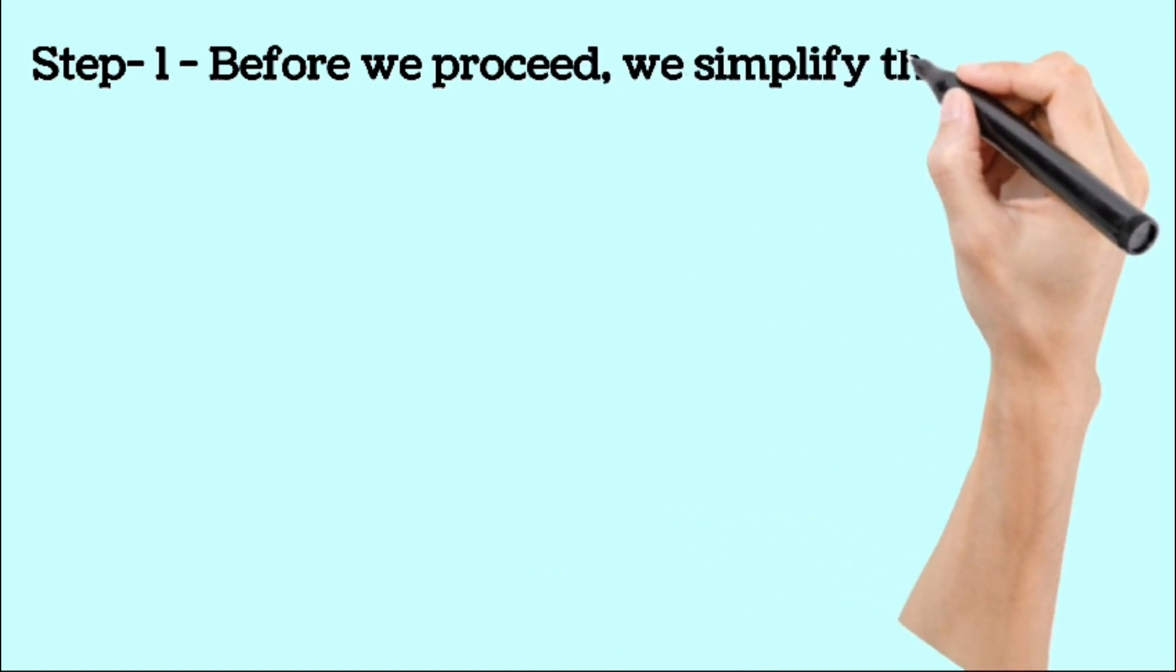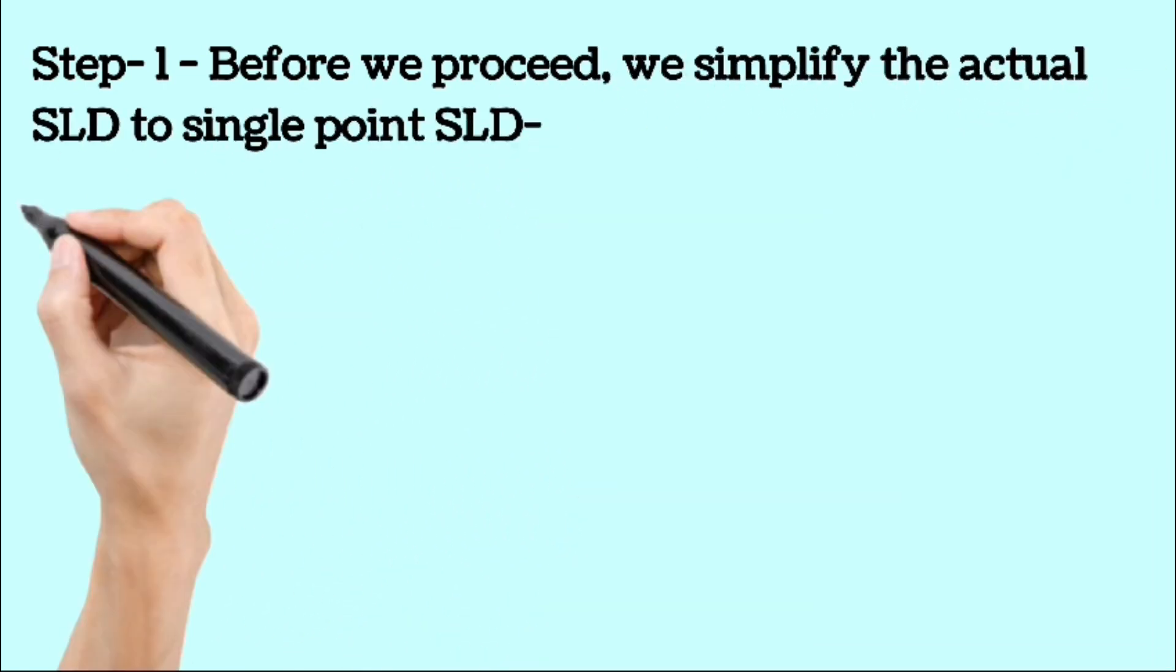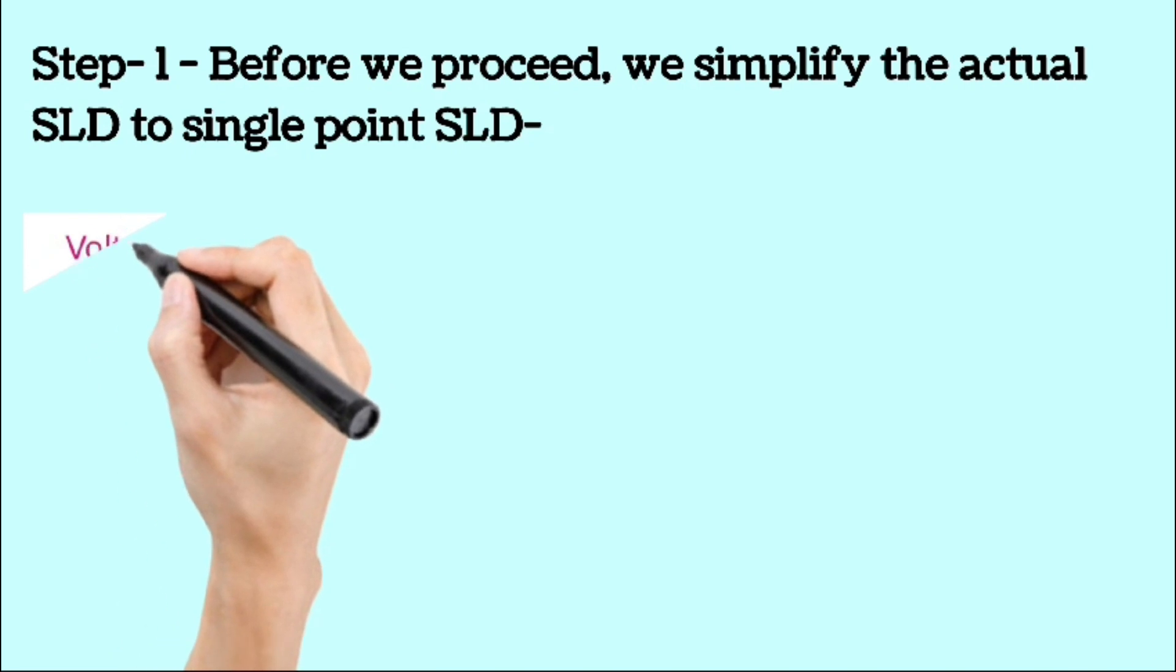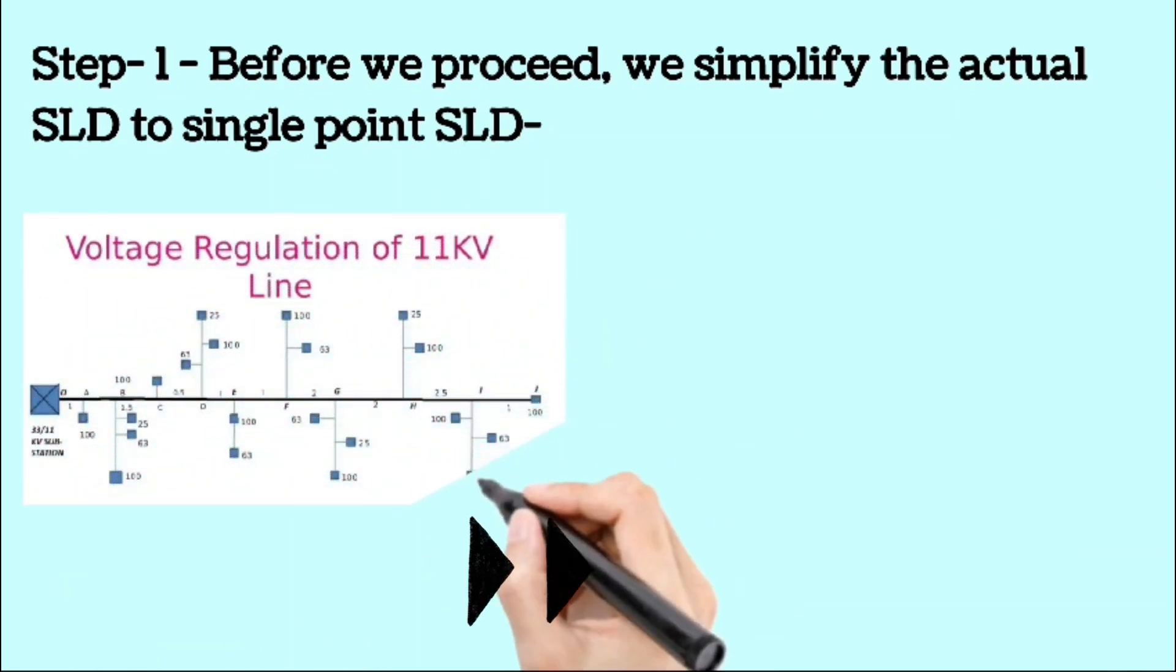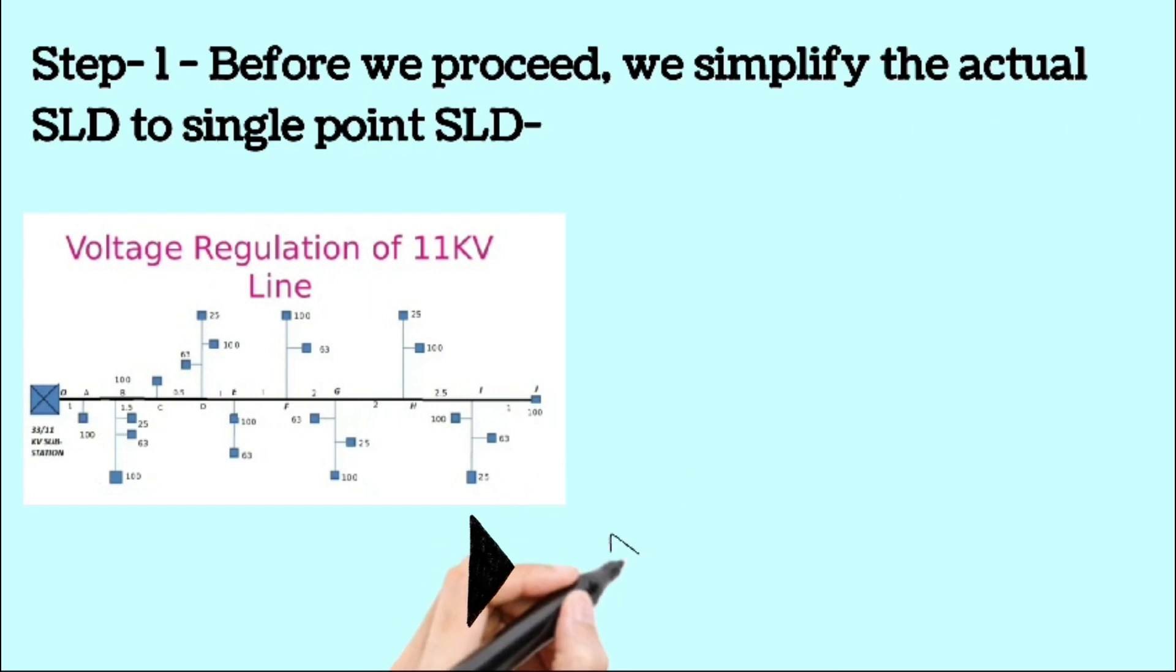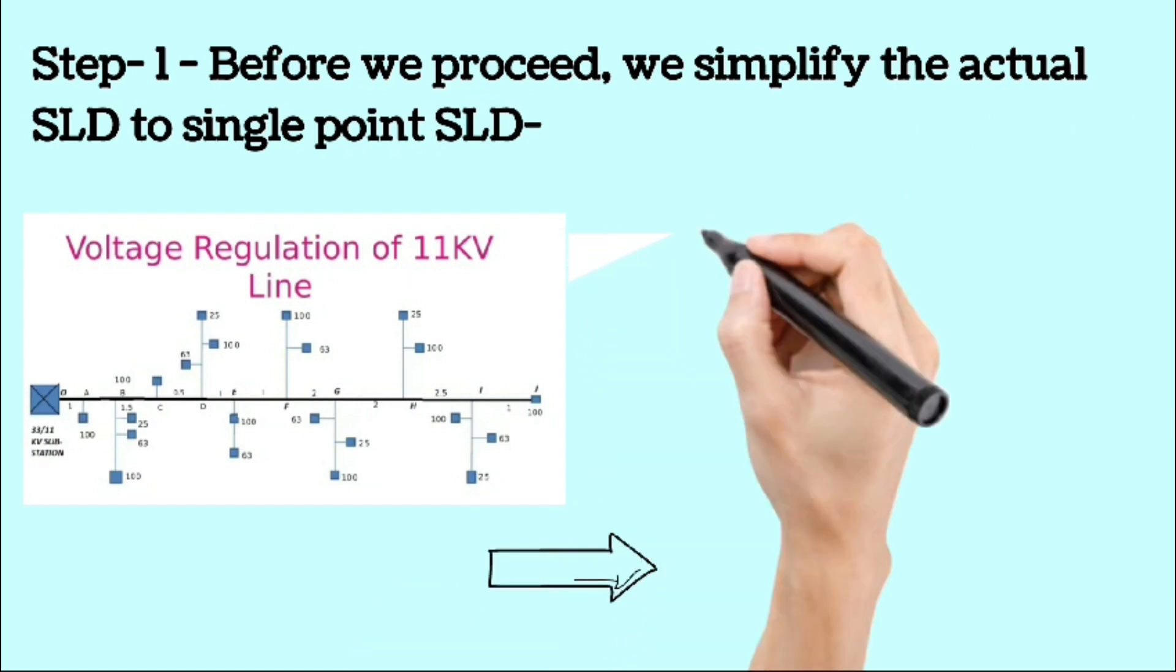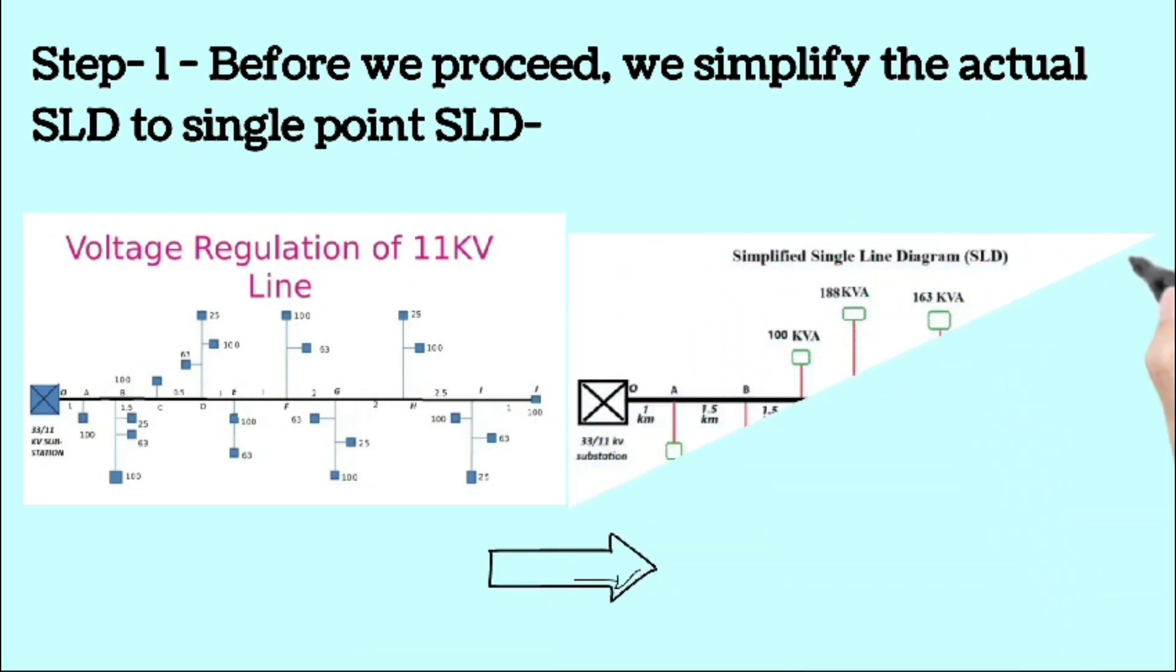Hey engineers, now we try to simplify the actual single line diagram into a more manageable single line diagram. This simplified diagram represents shorter tapping lines as point loads on the SLD. Remember, the tail end should be identified as the point farthest from the source. We add all load of each taping and make one point load as given in this diagram.